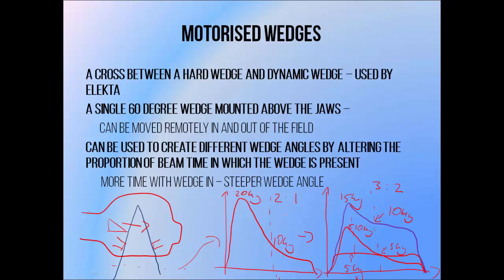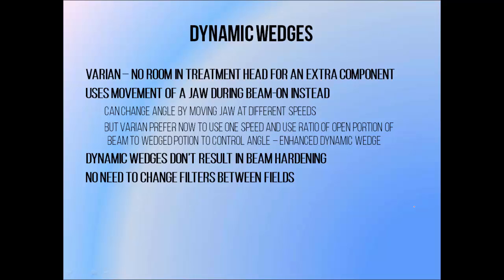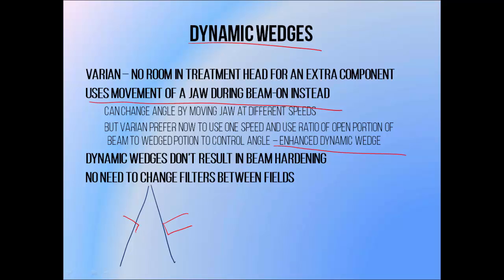A greater proportion of the beam delivered with the wedge in place means a steeper wedge angle. Varian have already added an MLC to their treatment head, so they don't have room for an extra component. Instead of adding a motorized wedge, they create wedged fields by moving the secondary collimator jaw through the beam while it's still on. This is known as dynamic wedging. Varian uses something called an Enhanced Dynamic Wedge, or EDW, which is similar in approach to the motorized wedge — a single jaw speed, so a single wedge angle, delivered in combination with an open beam to generate different wedge angles. Because we're not passing the beam through a filter, it doesn't result in beam hardening or affect the spectrum of the beam. And just like Elekta's motorized wedge, it can be controlled from outside the treatment room, allowing for faster treatment times.